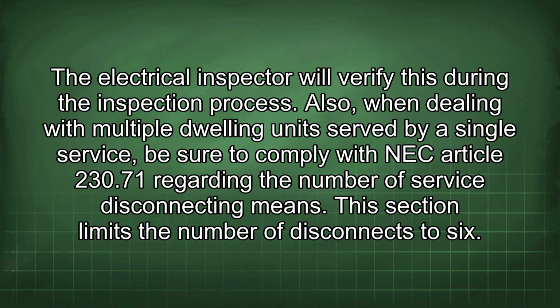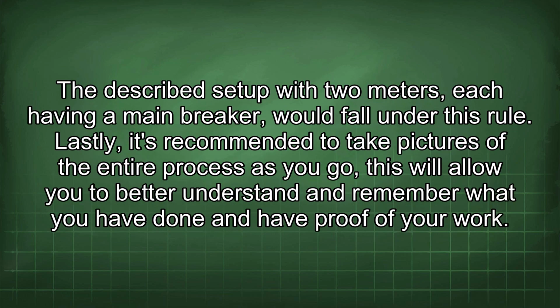230.71 regarding the number of service disconnecting means. This section limits the number of disconnects to 6. The described setup with 2 meters, each having a main breaker, would fall under this rule. Lastly, it's recommended to take pictures of the entire process as you go. This will allow you to better understand and remember what you have done and have proof of your work.